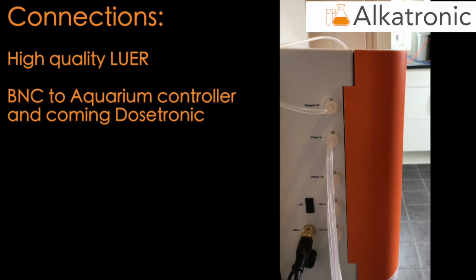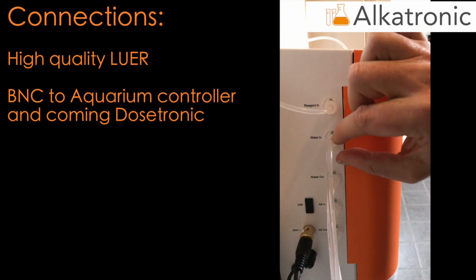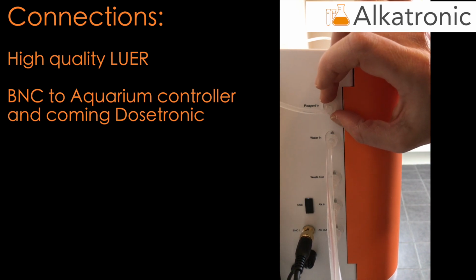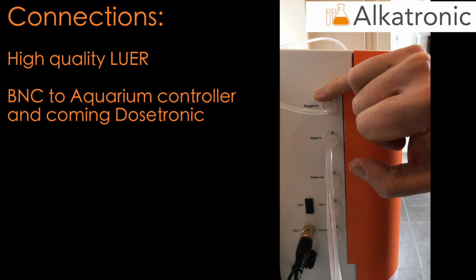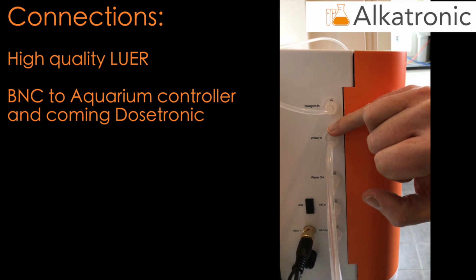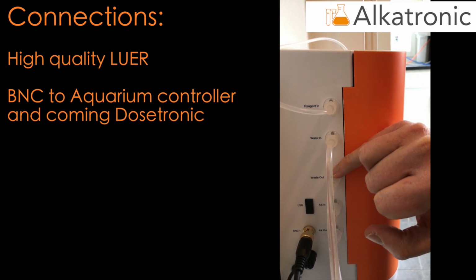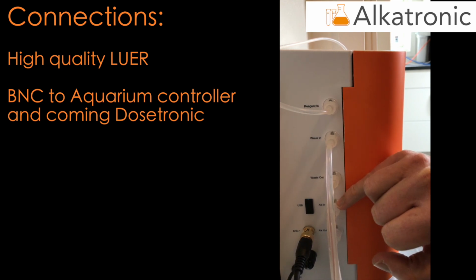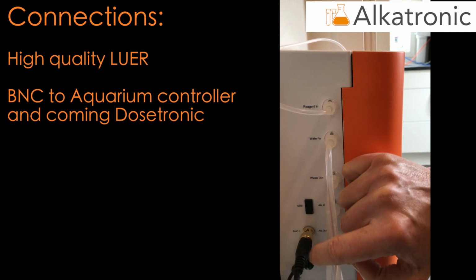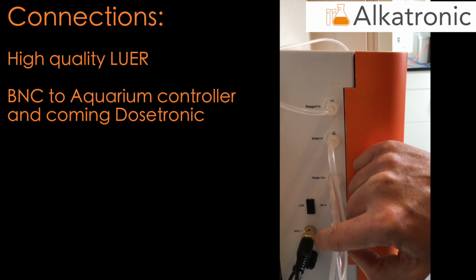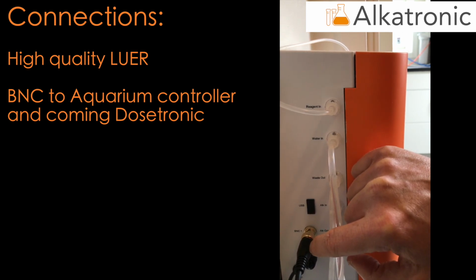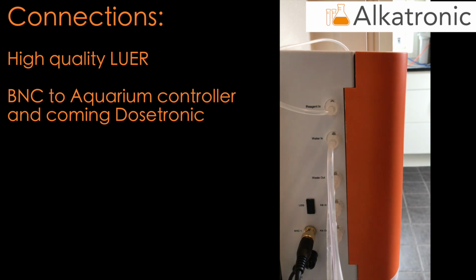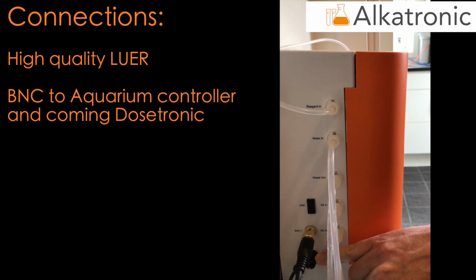On the side of the machine we have high professional Luer fittings, which are the same sort that are used in medical care. We have the reagent in, the water in to be tested, the wastewater out, alkalinity solution in and alkalinity solution out. Here we have the BNC connection for transferring information to a third-party aquarium computer, for example an Apex or GHL, USB for the update, and another BNC connection for a further Dosetronic.